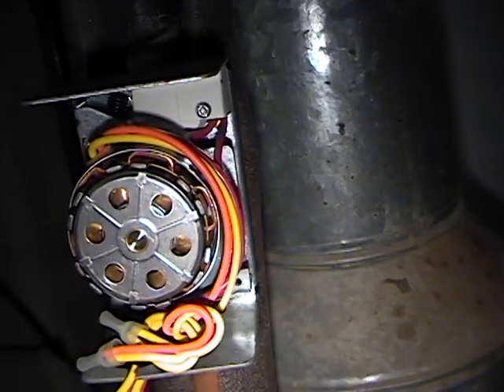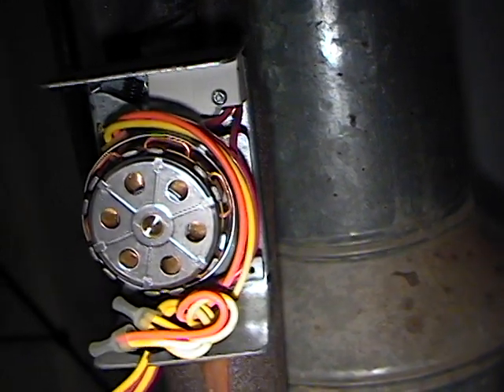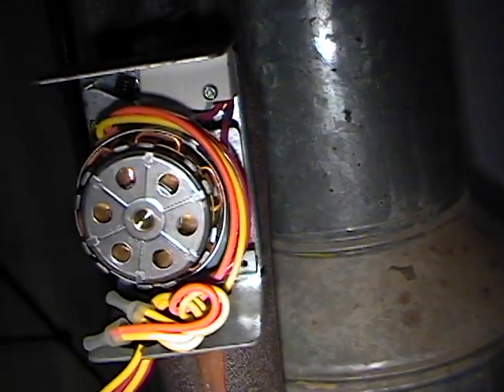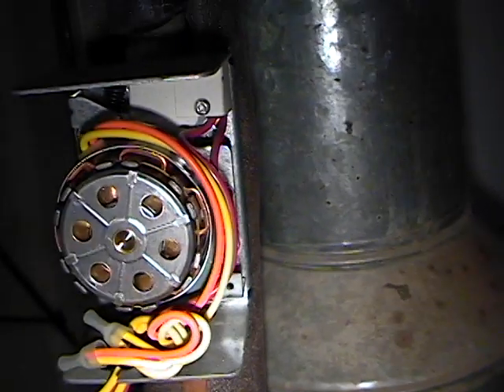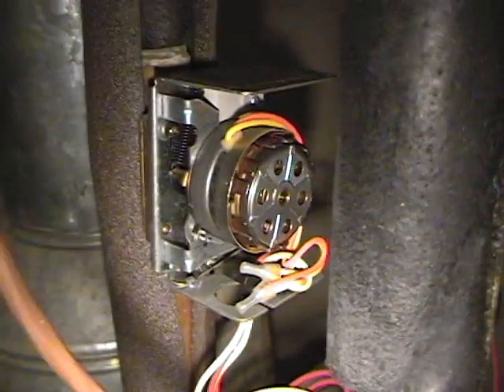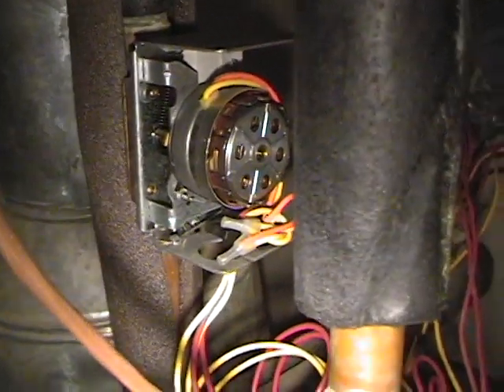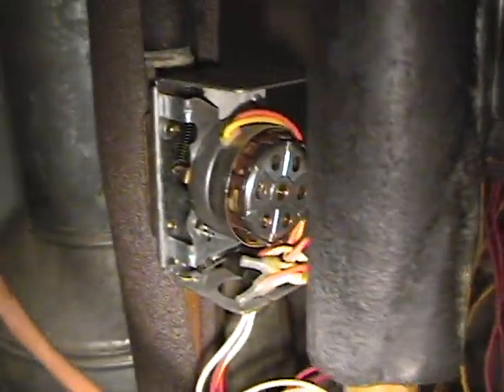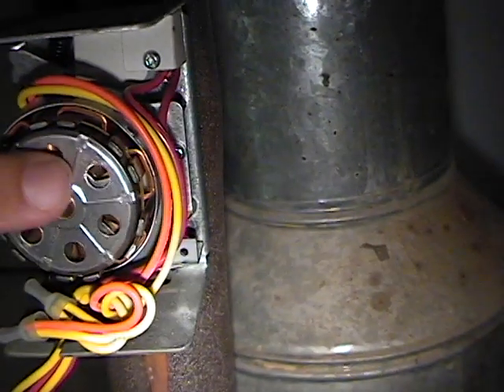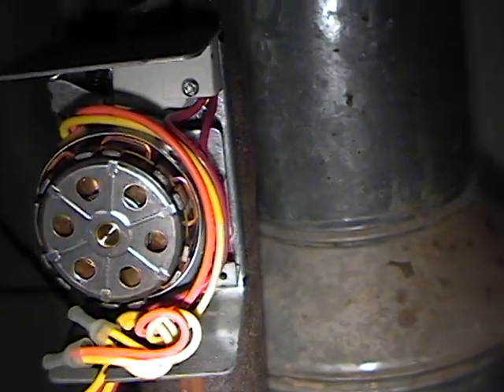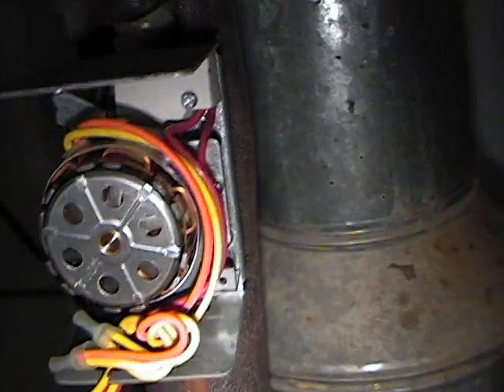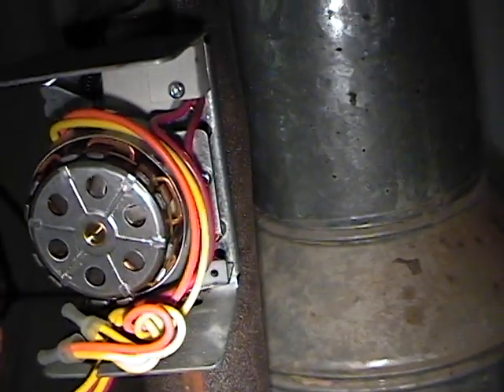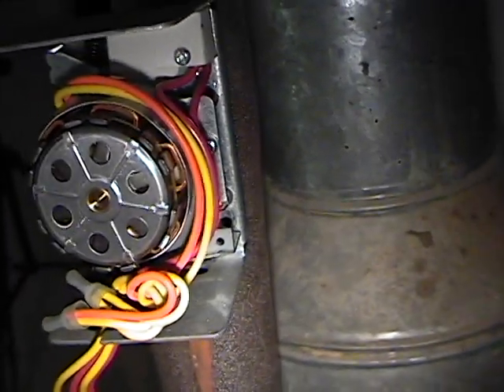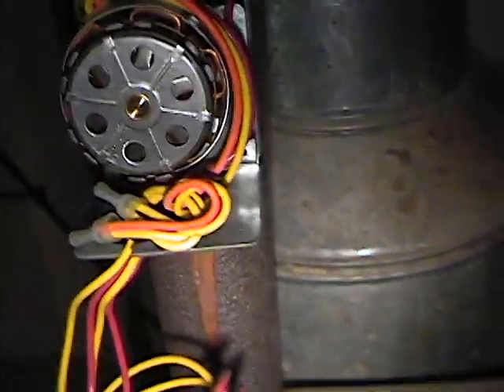Okay, yeah, do you see those windings right there? When the valve becomes energized, it forces the disc to spin counterclockwise, which is the opening direction, and then it slowly opens up the valve, and once it's mechanically detected that the valve is open enough, it will turn on the boiler and allow the heating process to begin. And once the valve is fully open, the windings actually hold the disc in place, which holds the valve open. Unlike a regular motor, this doesn't always have to be turning when the windings are energized. It's not going to overheat or break down. It's designed to do that.